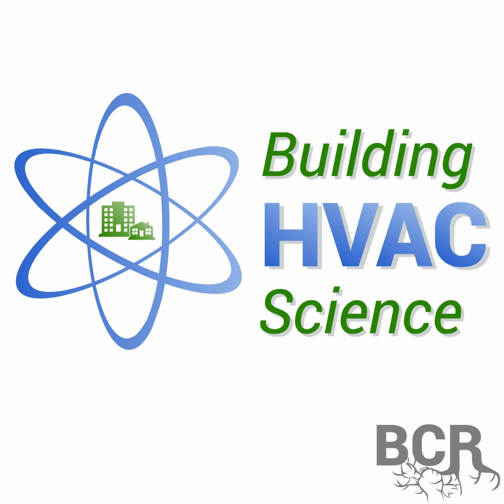But I did want to mention, the question comes up, well, if I have a hood that might have a lot of insertion loss, but it's fairly accurate in most cases, is that good enough? Or conversely, if I get a hood that doesn't have much insertion loss, but it's not real accurate, could I just say, well, it's always going to measure 20% high, so I'll still get a balance? And the answer to both of those questions is no, it doesn't work. The reason for that is if I get a hood that's off by 20%, it's not consistently 20% high or 20% low. In most cases, it will depend on which way you put it on the register, and is the register on the left side or the right side or the top or the bottom? And in terms of insertion loss, you'd like to think, well, if my hood creates an insertion loss of 20%, isn't that just going to cause all my registers to be low by 20%?